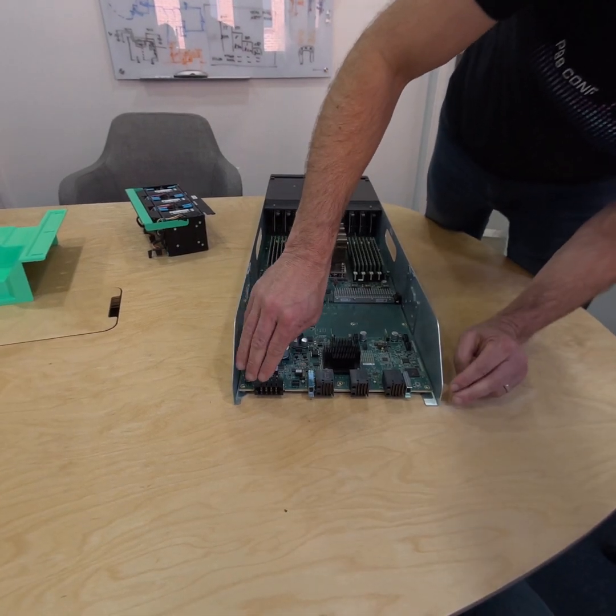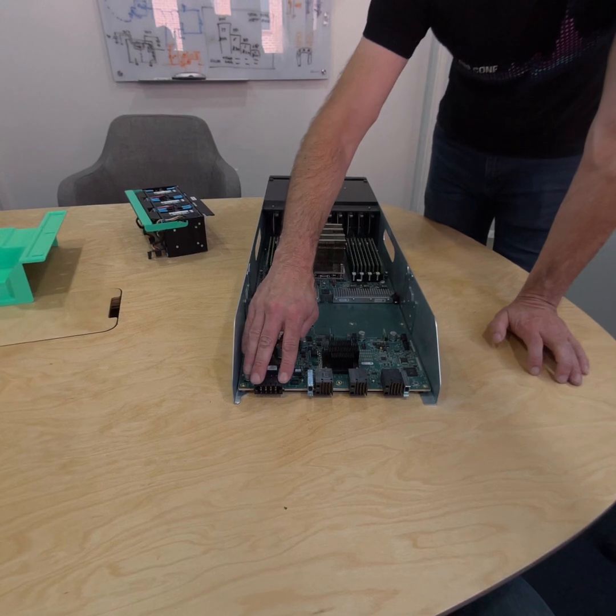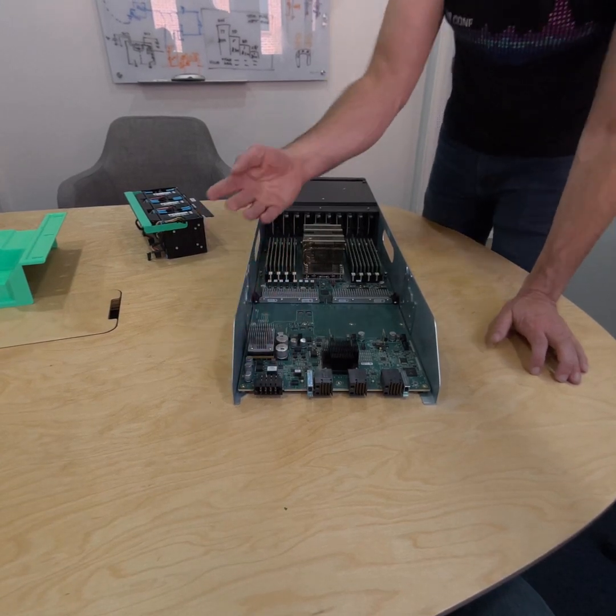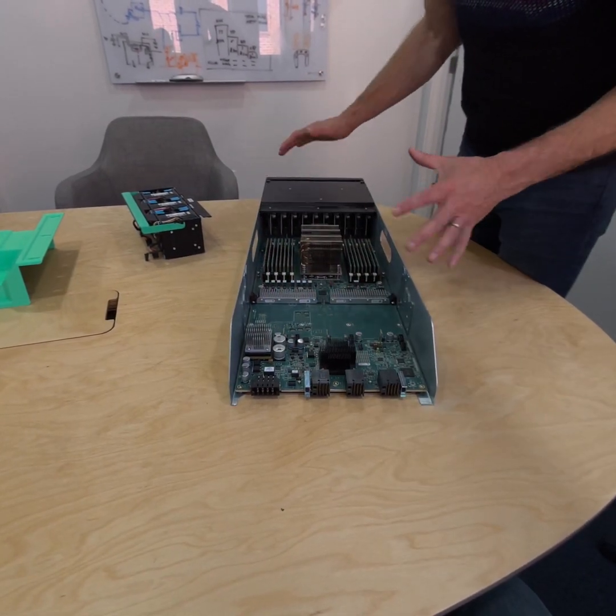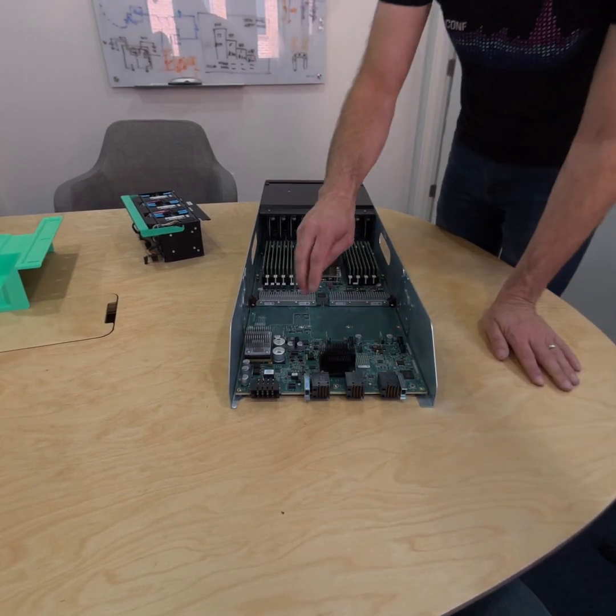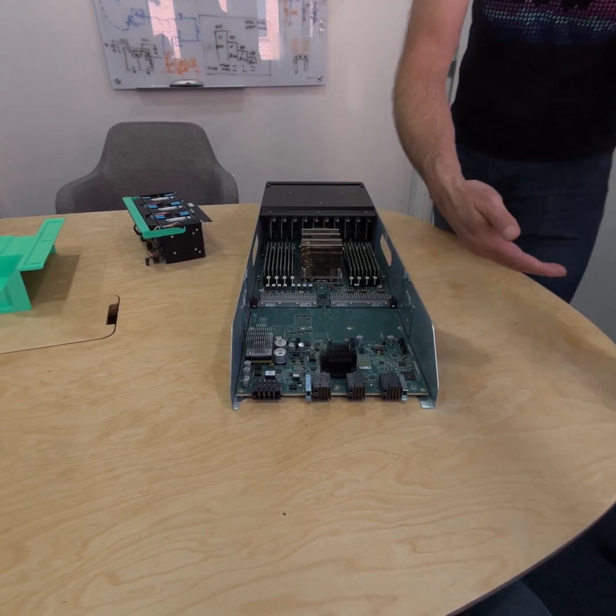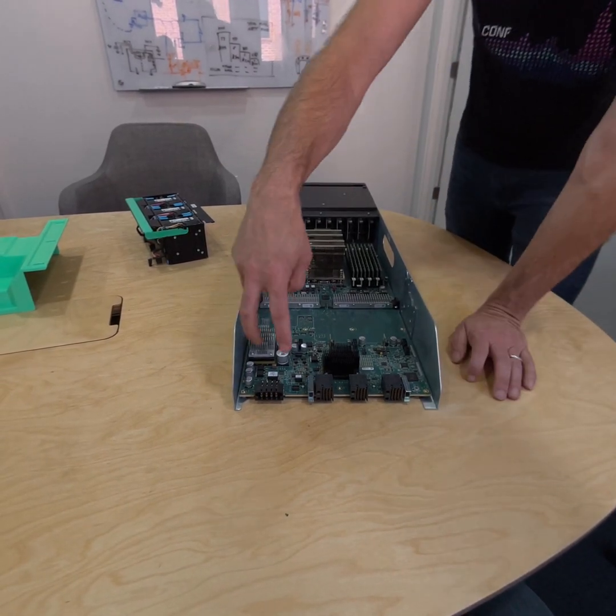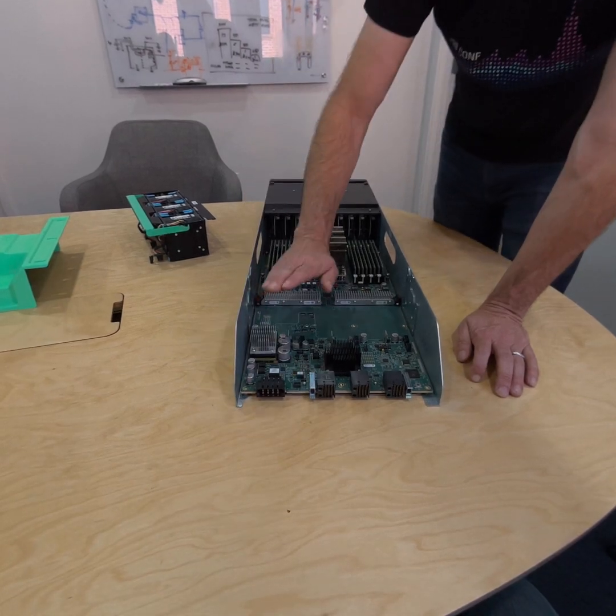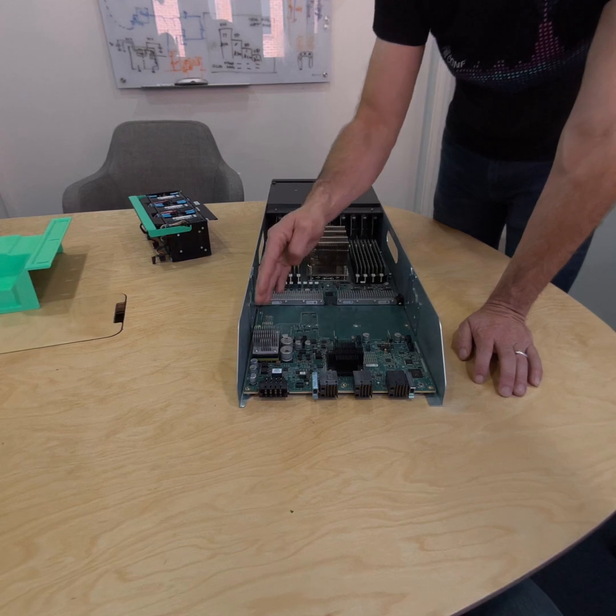Back here we have a couple of connectors. This is our power connector — it blind mates into DC power. In this compute sled there's no AC power supply; we've got DC coming in from the bus bar. We've got our rectifiers and power shelf plugging in AC power there, turning it to DC.